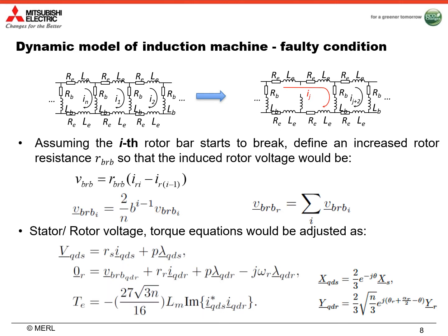In faulty condition, the dynamic model of induction machine needs to be changed accordingly. Let's assume the k-th rotor bar starts to break. We define an increased rotor resistance such that the induced rotor voltage can be expressed using this equation. Accordingly, the stator voltage, rotor voltage, and torque equations would be adjusted as shown in the following equations.